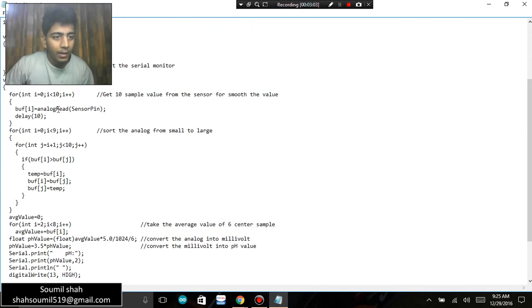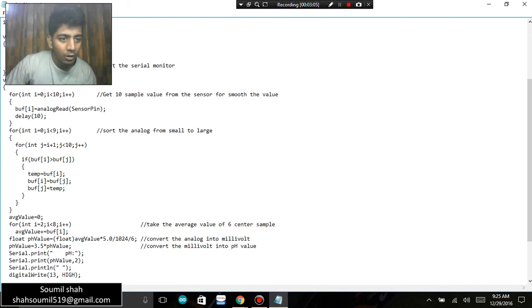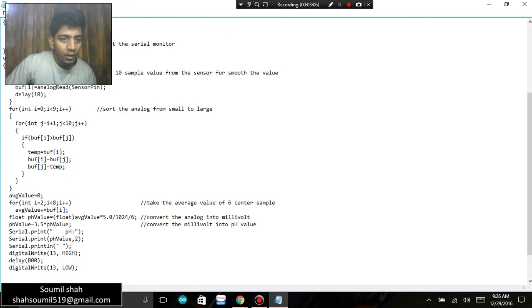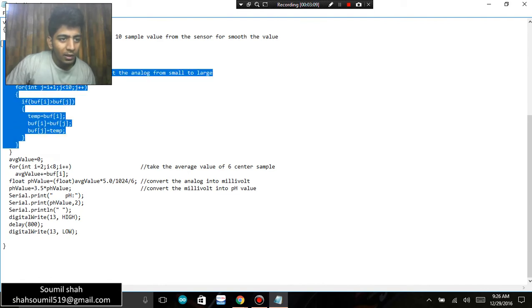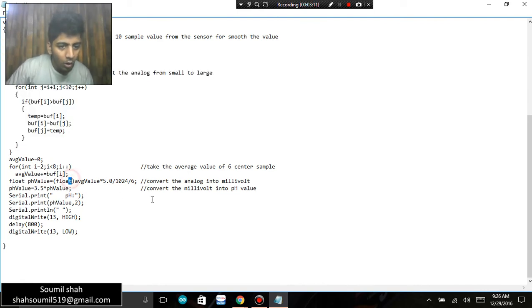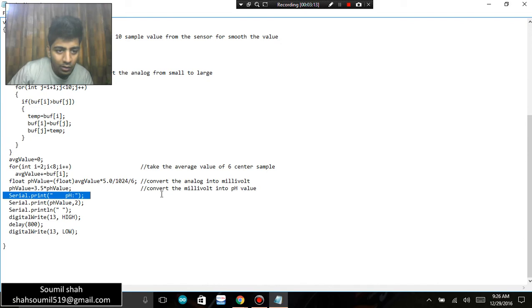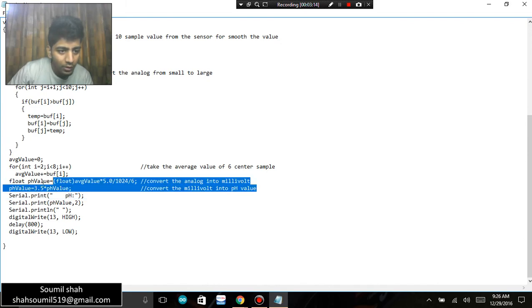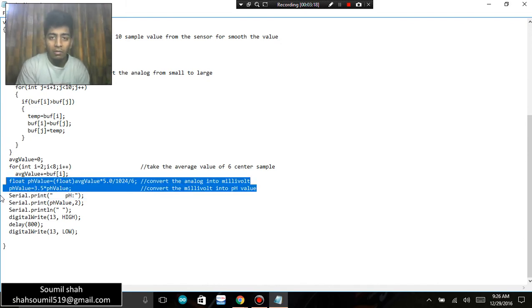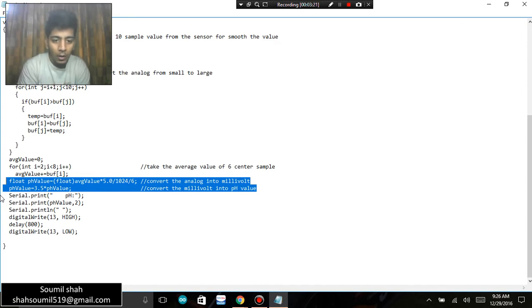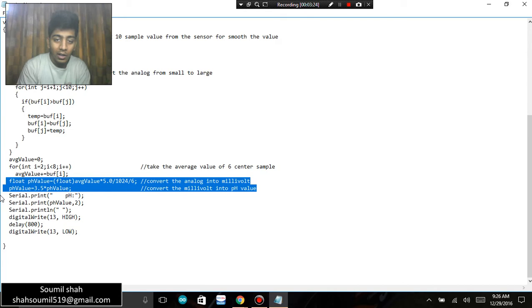What's important is these two lines. Now what we are trying to do here is whatever values we get, we are trying to convert that into millivolts. The analog value we are trying to convert into millivolts, so the conversion is given below, and then we are trying to convert that millivolt into a pH value.